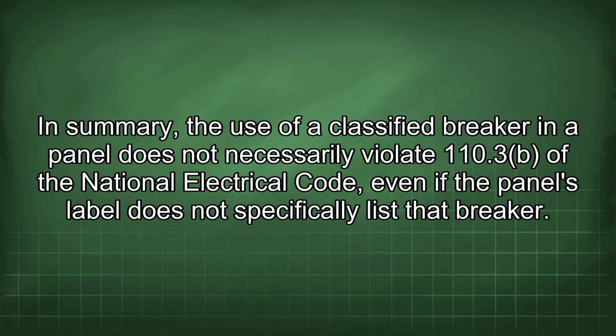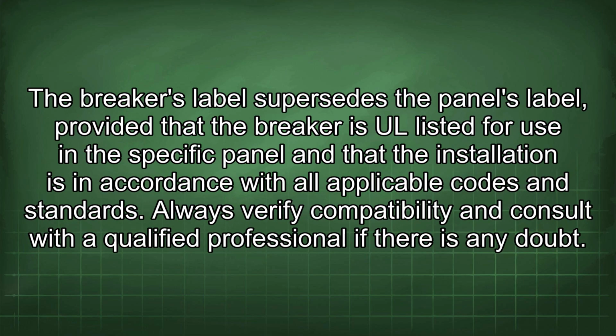In summary, the use of a classified breaker in a panel does not necessarily violate 110.3 of the National Electrical Code, even if the panel's label does not specifically list that breaker. The breaker's label supersedes the panel's label, provided that the breaker is UL listed for use in the specific panel and that the installation is in accordance with all applicable codes and standards.